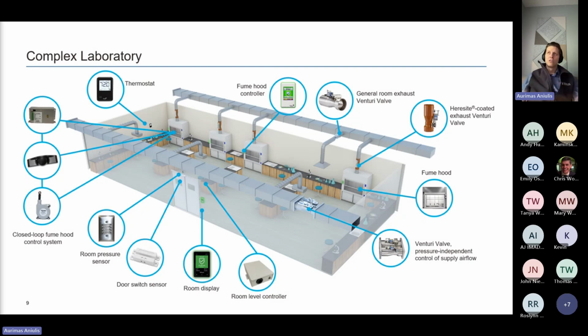balance the room. So in this scenario, the way we think about pressure control is that the fume hood is most negative, and it's got to be negative to the room so nothing can escape the fume hood work area into the lab zone. And if it did, the room is negative to the adjacent spaces like the hallway, so that nothing would escape from the lab into the adjacent room, grow a pair of legs, run off to the local market, and cause a national pandemic, right? We just don't want that. It's bad for business.